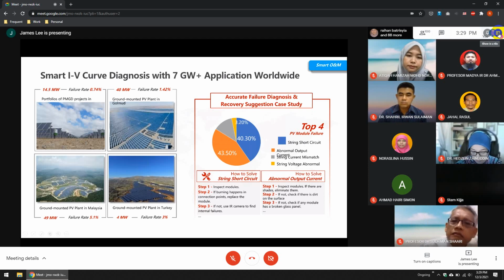From there, you'll be able to identify certain panel failures. We found through 7 gigawatts worth of applications that one of the top 4 module failure types are string short circuit, abnormal output current, string current mismatch, and string voltage abnormal. These things are not commonly easily seen by the naked eye, and you would have to have a thermograph scanner in order to identify the hotspots or whatever signs indicate this.